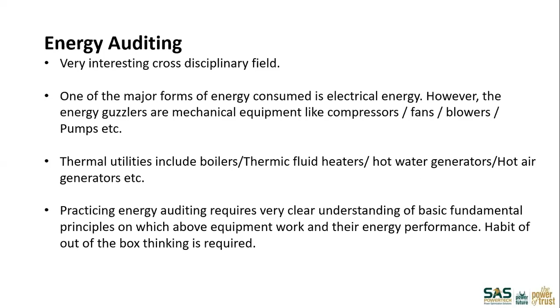Another thing is a system engineering approach is very much necessary for energy auditing. By system engineering, I mean the entire system needs to be considered as a block, and then energy efficiency has to be analyzed. A small example: an energy efficient motor connected to an energy efficient pump may not necessarily form an energy efficient pumping system, because you might operate that pump way off from its best efficiency point. If that happens in the design, then even though both pieces of equipment are energy efficient, the total system will not be energy efficient. You always have to think about the entire system you are connected with, or which you are trying to audit.